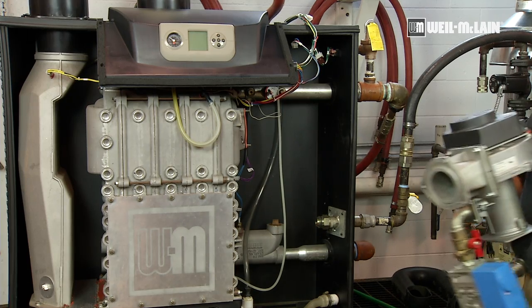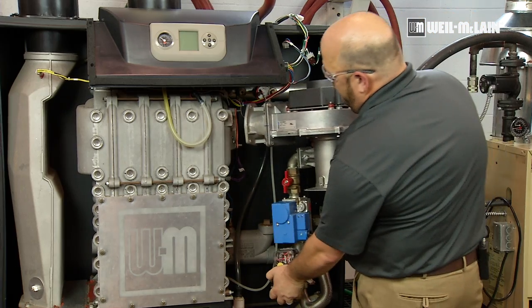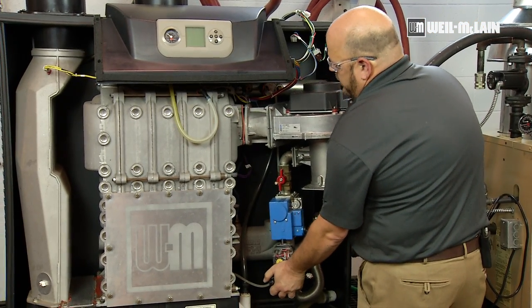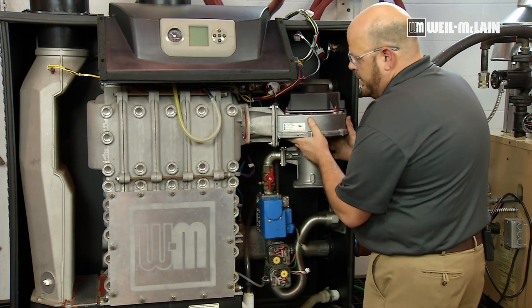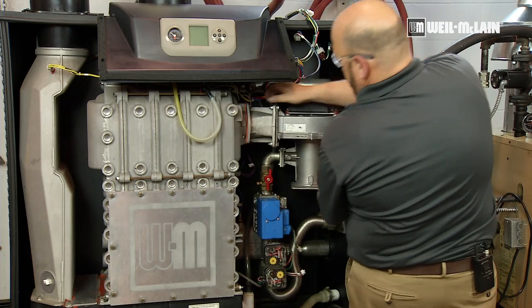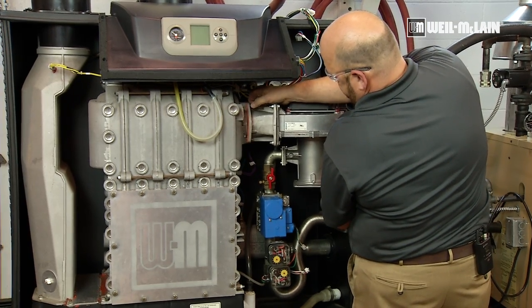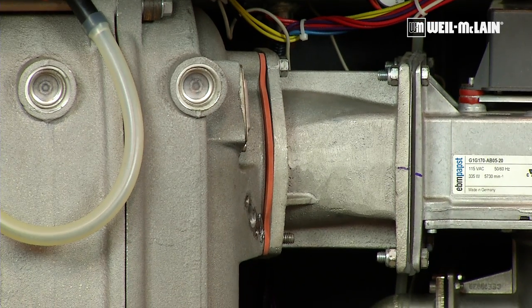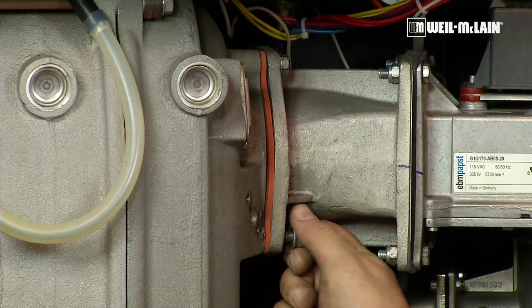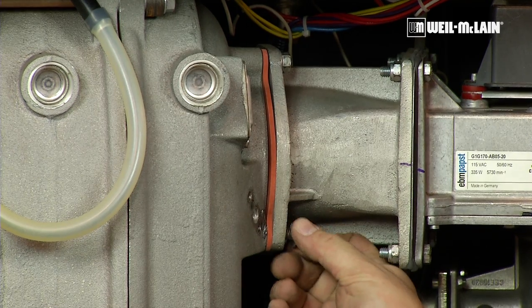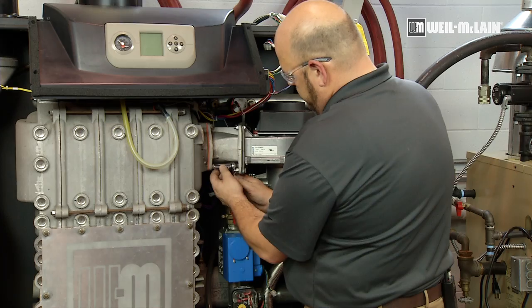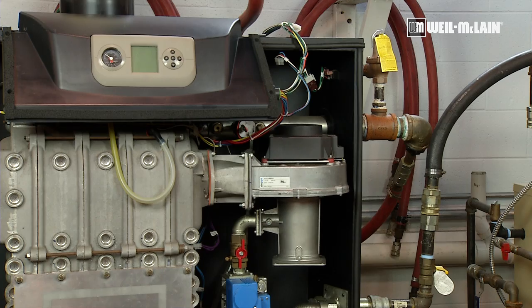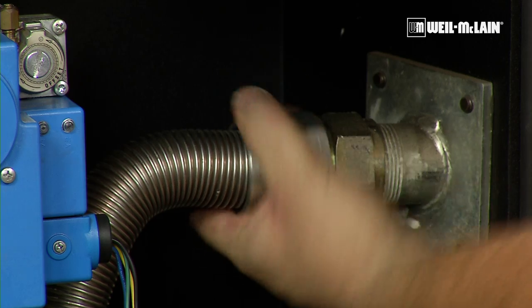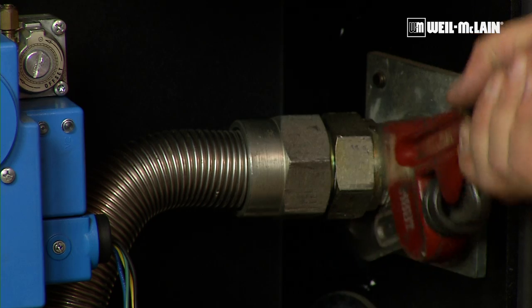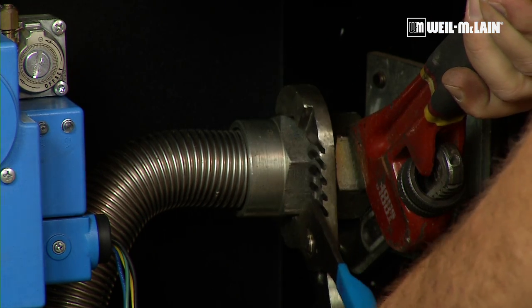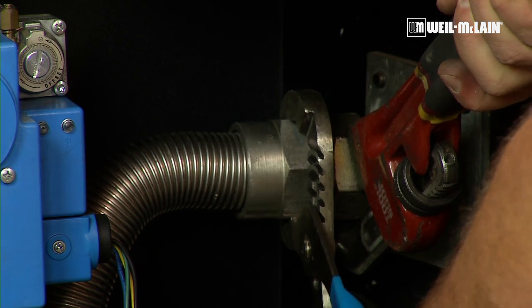Now we'll put our combustion assembly back into the boiler. If you match the two holes that are most forward on the flange for the adapter, and then rock the back into place, and you can slide it right in. Put your top bolt on to retain, and add your other two bolts onto the flange. So now we have our blower back into place. We can hook our gas line. So we have one wrench below, one above to tighten the nut into place.